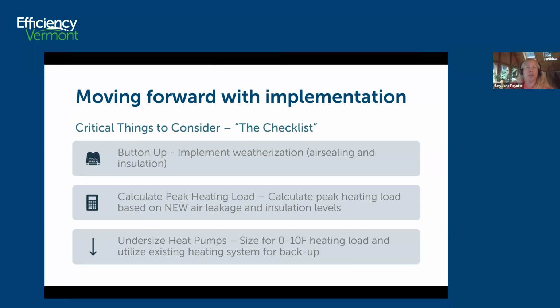Here are the really critical things that I think these discussions need to be had with the customer before getting to the point of installing something. Number one is buttoning up, and that would be the phrase we use quite a bit for doing air sealing and insulation. That's the number one thing that should happen in the building. The second is to recalculate the peak heating load, because the original heating load was designed for the original building, and there may have been some safety factors in there. So we really want to look at what the new peak heating load is, factoring in the improvements in thermal shell.